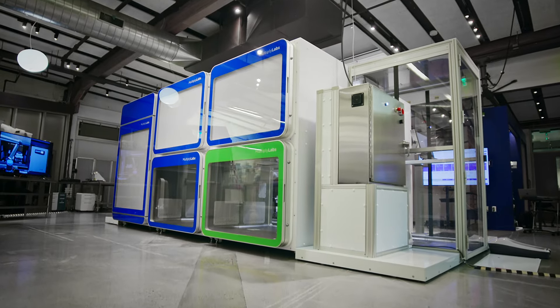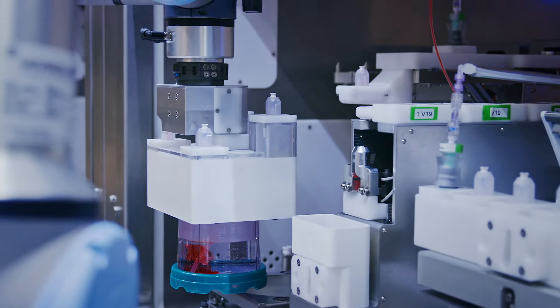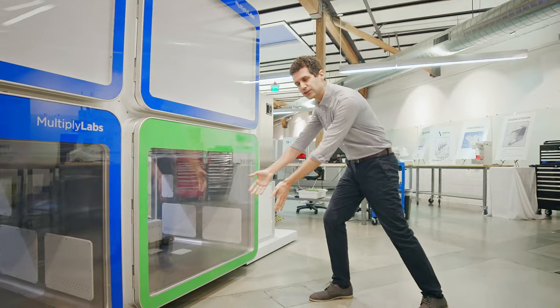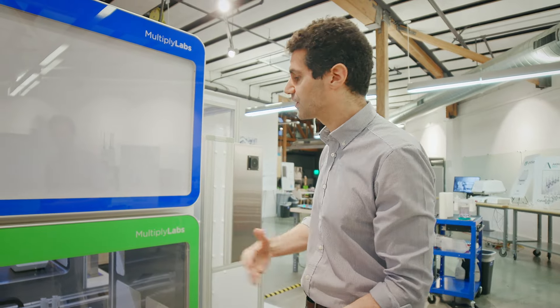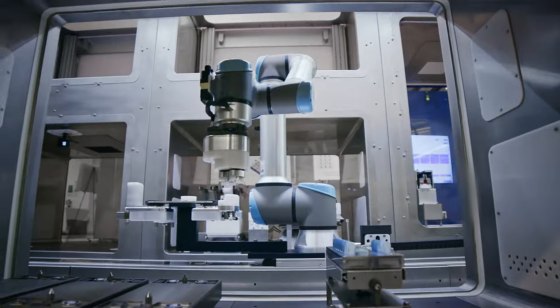It's very important to make sure that everything that gets in is not contaminated and sterile. We do that through the only green module. An operator would insert cartridges or retrieve products. Vaporized hydrogen peroxide is released in order to sterilize everything. The most frequent source of contamination are human operators.